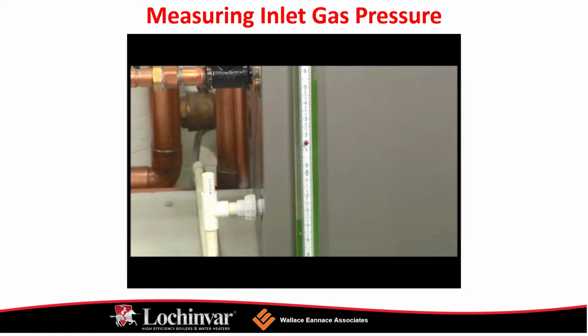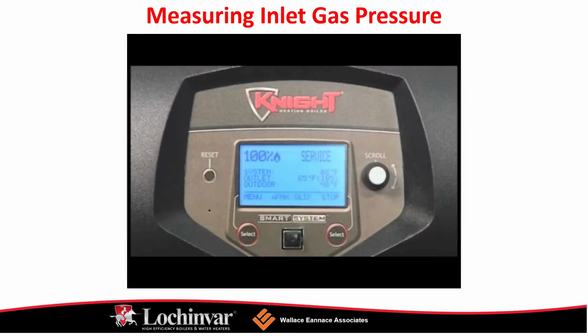If the static inlet gas pressure is adequate, the inlet gas pressure under load may be checked. Turn the on-off switch to the on position. Locate the pinhole button on the display. Using a paper clip or something similar, press and hold the button for 5 seconds. The word service will appear on the status line of the display. The unit will fire at its normal ignition speed and will then modulate its firing rate to 100%.